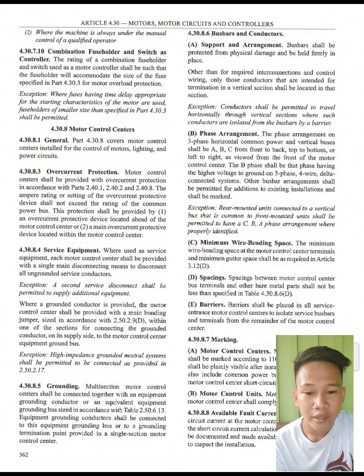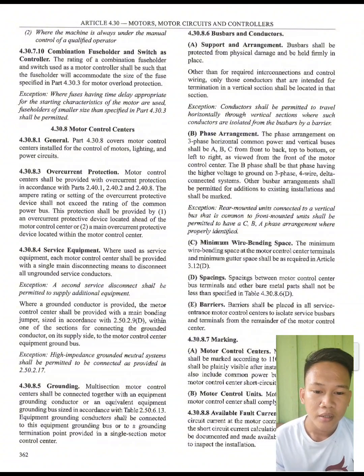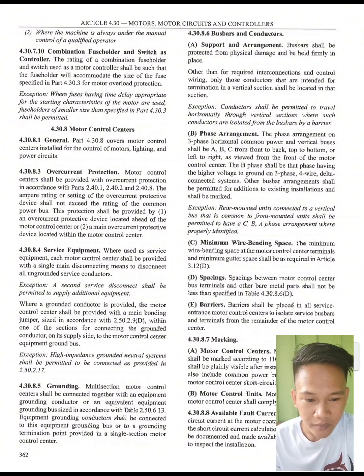So, 4.30.8.3 Overcurrent protection. Motor control centers shall be provided with overcurrent protection in accordance with Parts 2.40.1, 2.40.2, and 2.40.8. The ampere rating or setting of the overcurrent protective device shall not exceed the rating of the common power bus. This protection shall be provided by, first, an overcurrent protective device located ahead of the motor control center. Second, a main overcurrent protective device located within the motor control center.